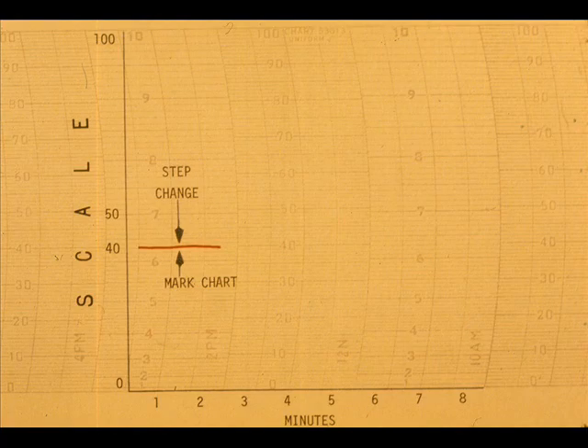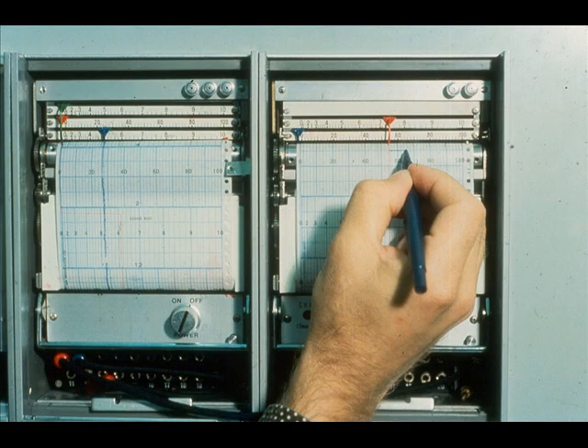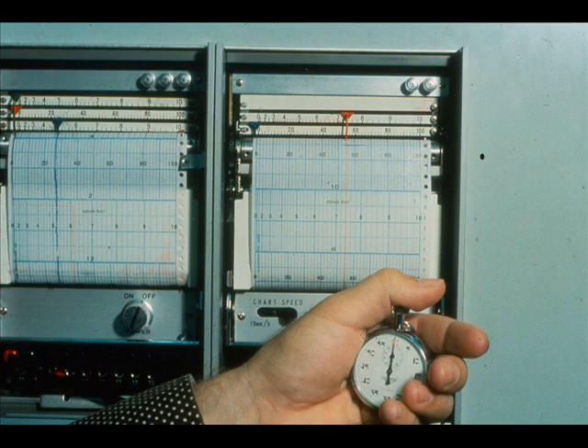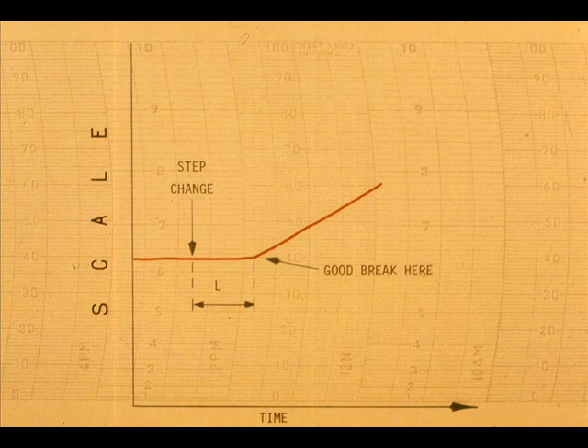Mark the chart at the exact time the manual step change is made — make the mark plainly. Use a stopwatch and measure the time where the response begins to make a change, and mark the chart again. This is time L. Watch the stopwatch and put a third mark on the chart equal to 2L. Try to time L where the curve makes a good, clean break.